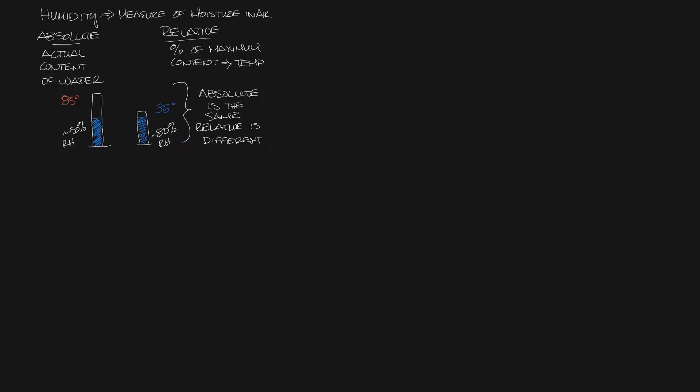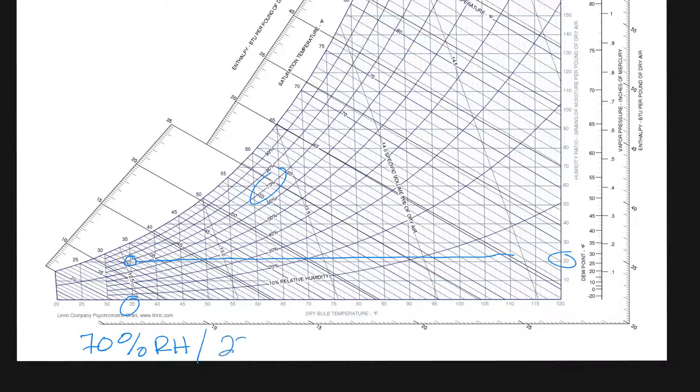Let's take this over to a psychrometric chart and look at this in real numbers. Let's look down here at 35 degrees and let's get the 70 percent humidity curve. Take this over to the right and you can see that we're probably about 22 grains is the absolute humidity.